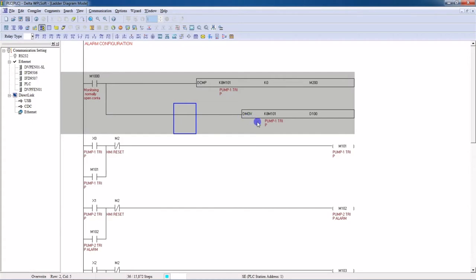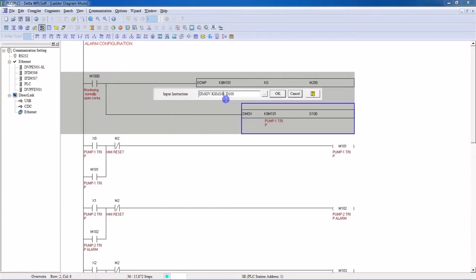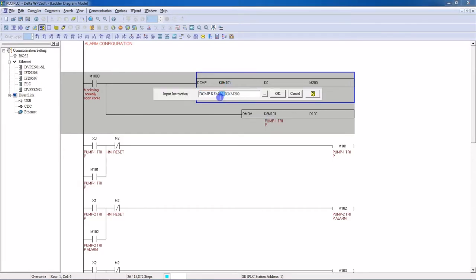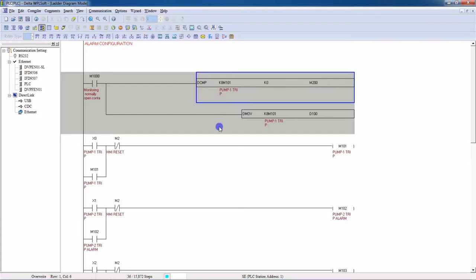Then in parallel I will move K8 M101 into D100. This D100 we are going to use in the HMI alarm register. Here you can see K8 M101, and this value should be placed in D100. If you have 10 alarms, then from M101 the next 10 bits will be used — it means M101 through M110 will be used in alarms.